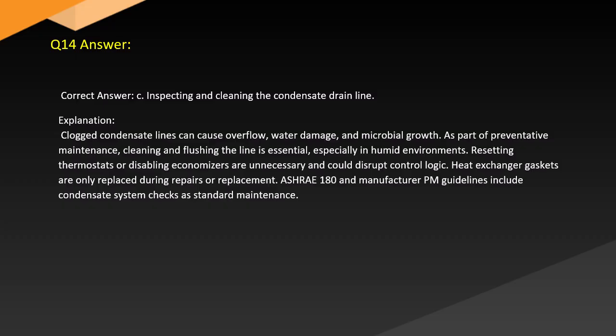Resetting thermostats or disabling economizers are unnecessary and could disrupt control logic. Heat exchanger gaskets are only replaced during repairs or replacement. ASHRAE 180 and manufacturer PM guidelines include condensate system checks as standard maintenance.